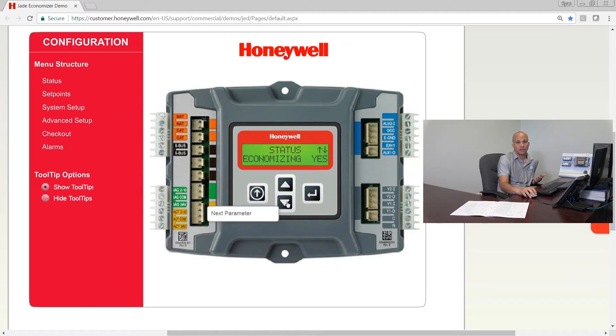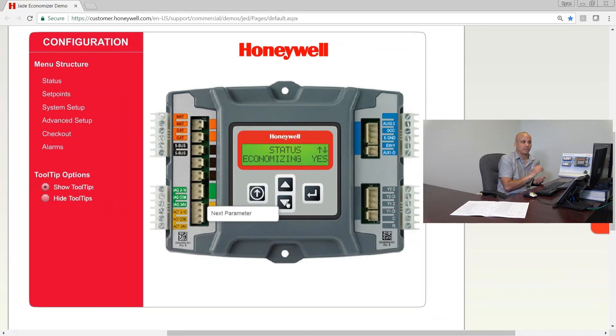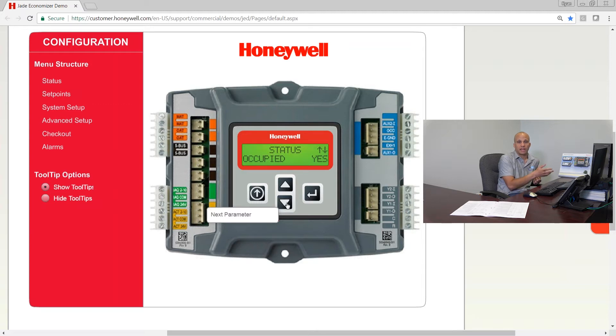Right now it's saying it's an economizer day. The next item is: is it actually economizing right now at this moment in time? So are we using outdoor air right now at this very second for our first stage of cooling? The thermostat asks for Y1 — is the economizer actually operating right now? Yes or no.